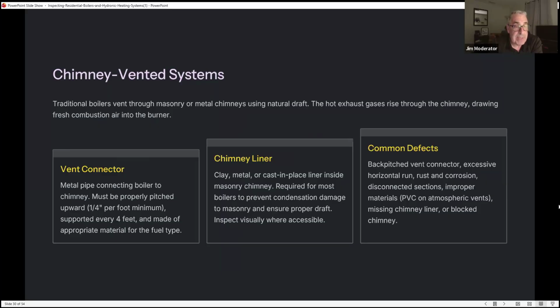Vent connector: a metal pipe connecting the boiler to the chimney. Must be properly pitched upwards, 1/4 inch per foot minimum, supported every 4 feet, and made of the appropriate material for the fuel type. Chimney liner: clay, metal, or cast-in-place liner inside a masonry chimney, required for most boilers to prevent condensation damage to masonry and ensure proper draft. Inspect visually where accessible. That's huge. You're not going to be able to see a lot. Common defects: back-pitched vent connectors, excessive horizontal runs, rust, corrosion, disconnected sections, improper materials, PVC on atmospheric vents, missing chimney liners, or blocked chimney.